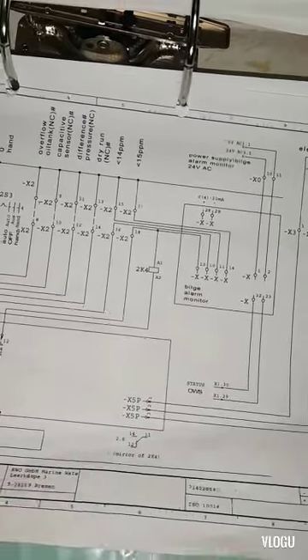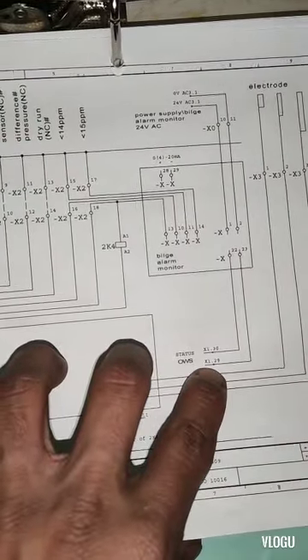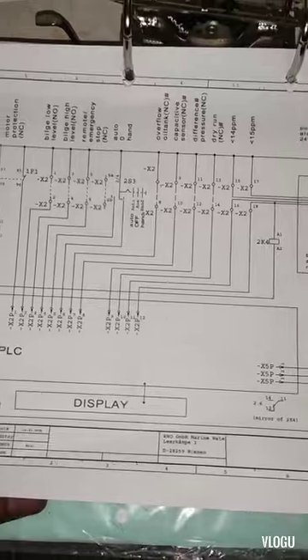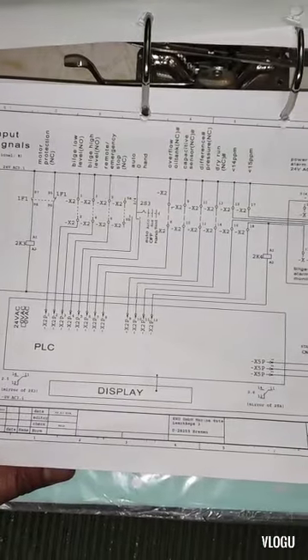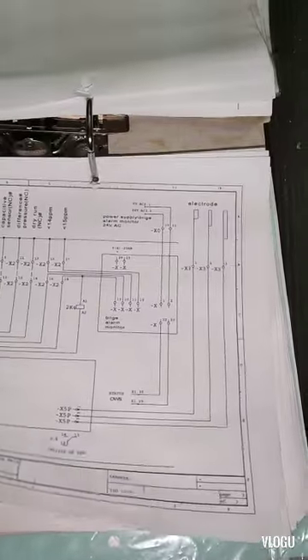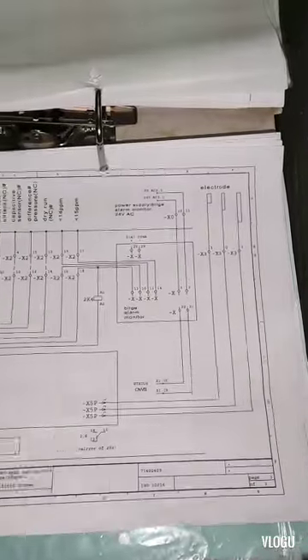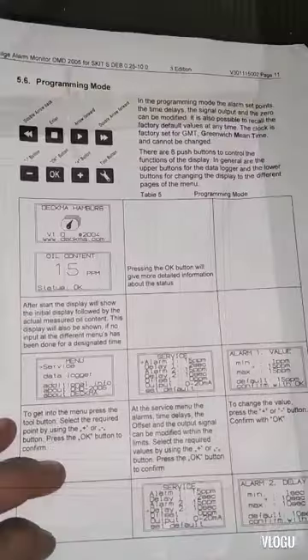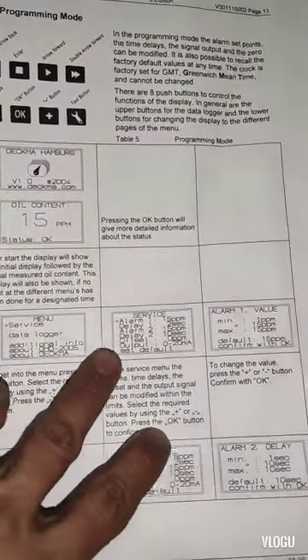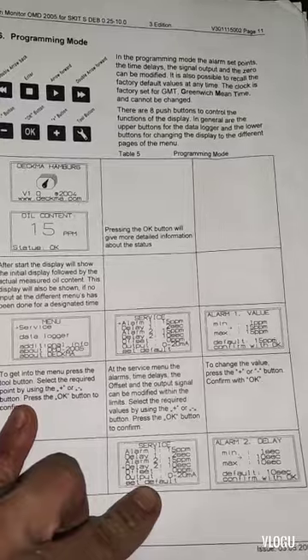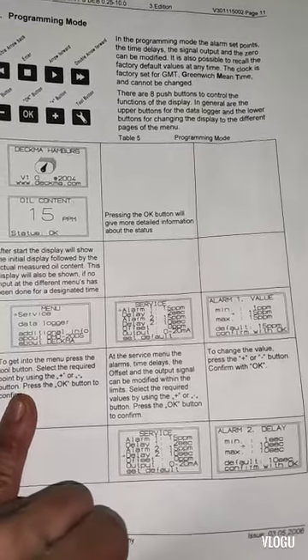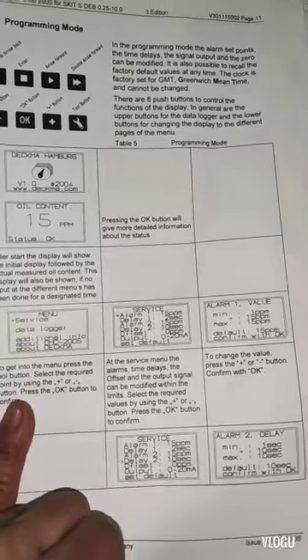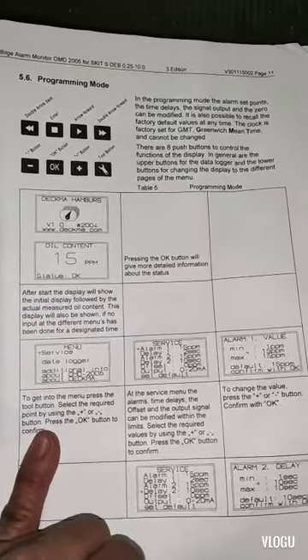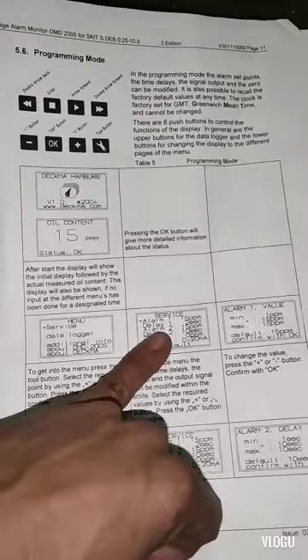Okay, we need to check the status signal X1, X30. And here I found the programming mode. Based on here, the alarm delay is 2 seconds and 10 seconds. Alarm 1 and alarm 2. For alarm 2 it is 10 seconds. For alarm 1 it is 2 seconds.